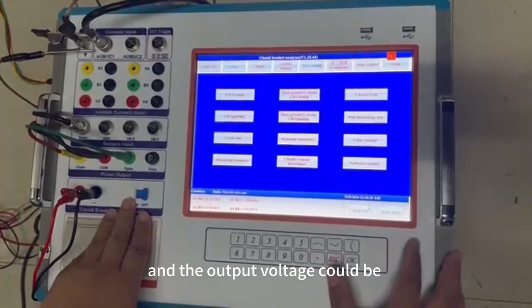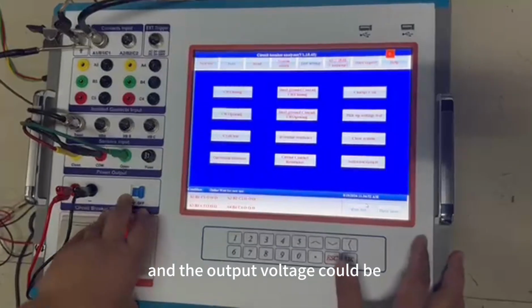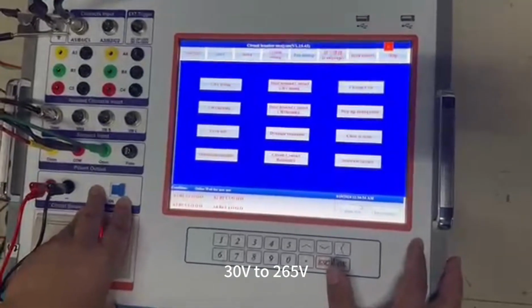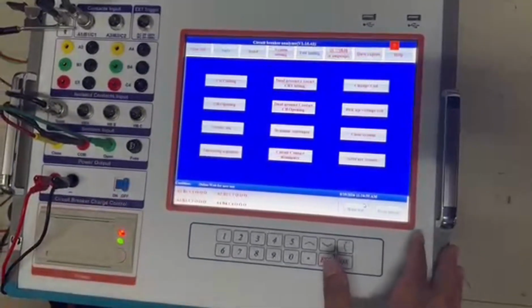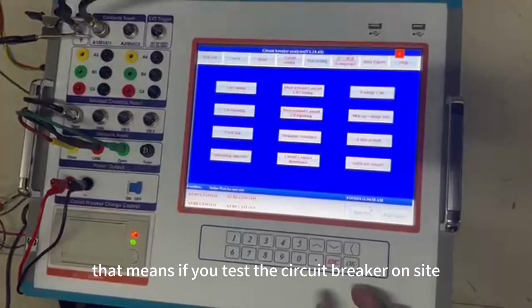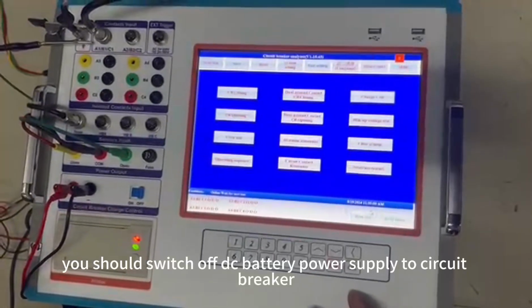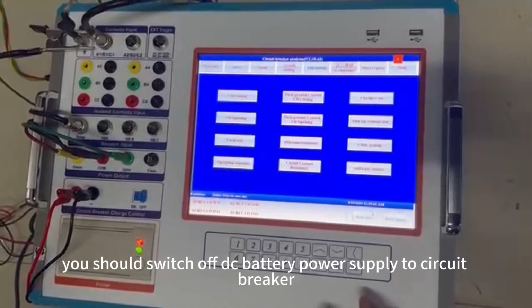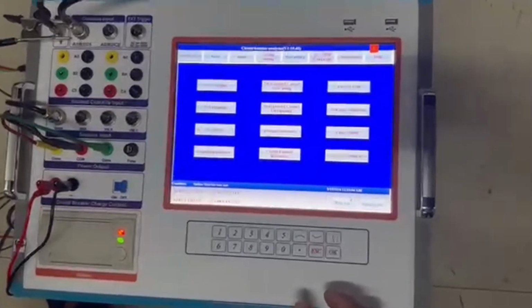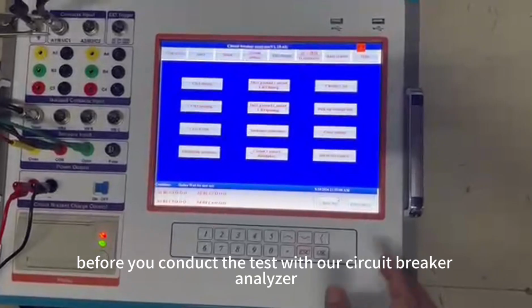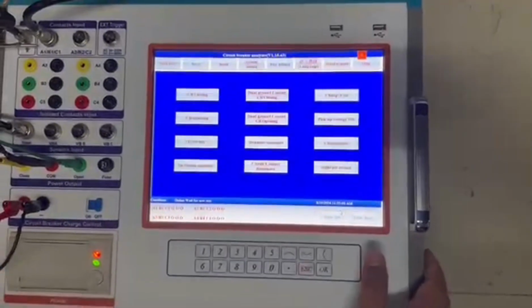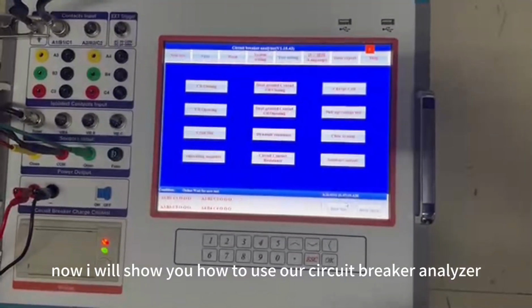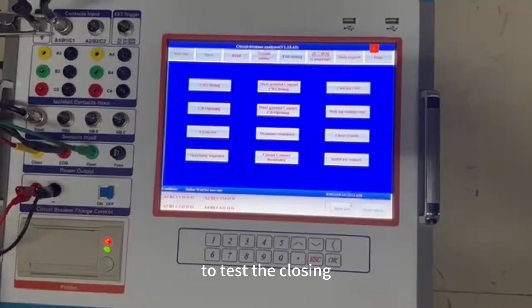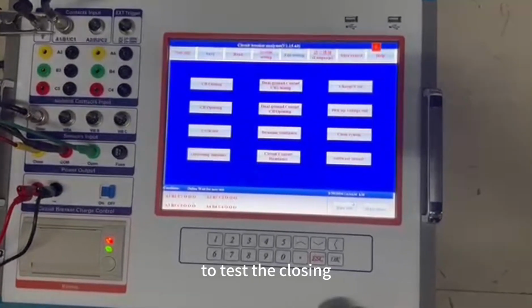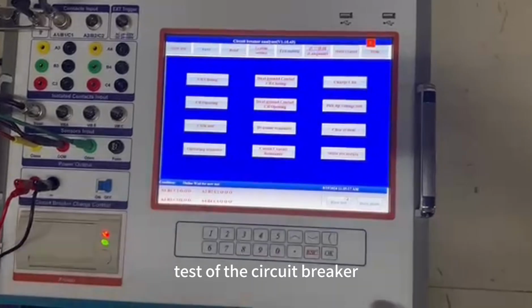The output voltage could be 30 volts to 265 volts. That means if you test the circuit breaker on site, you should switch off the DC power supply to the circuit breaker before you conduct the test with our circuit breaker analyzer. Now I will show you how to use our circuit breaker analyzer to test the closing test of the circuit breaker.